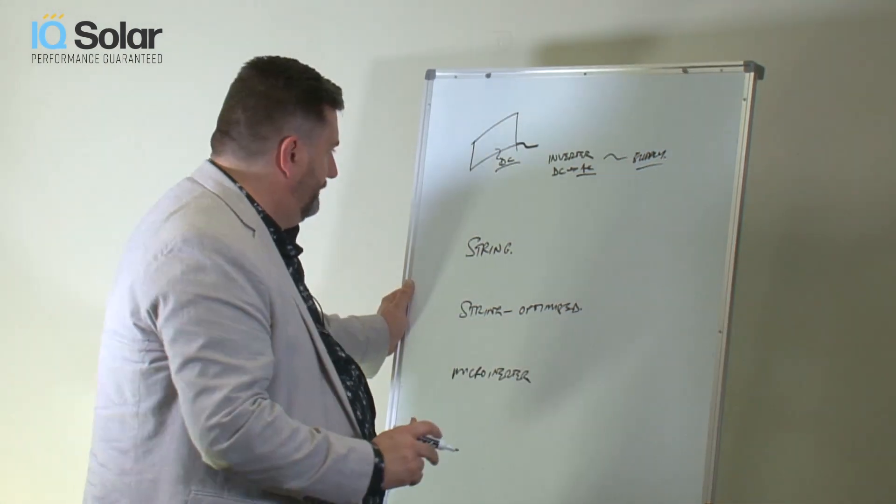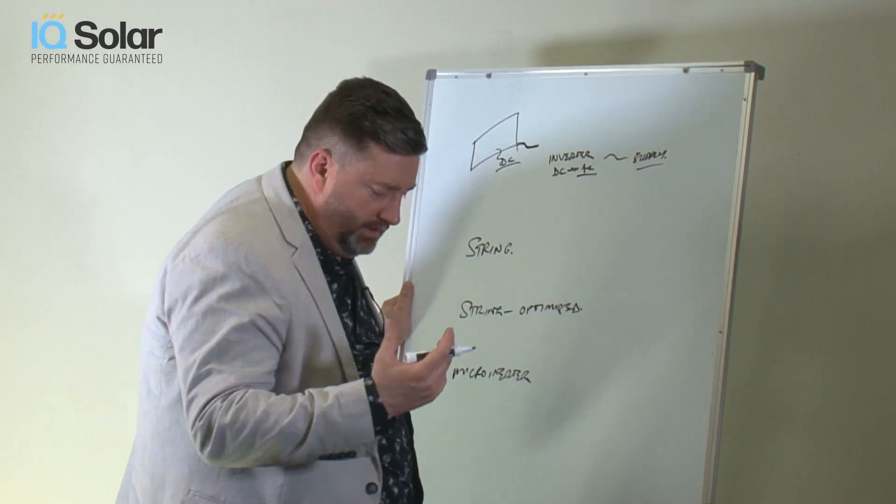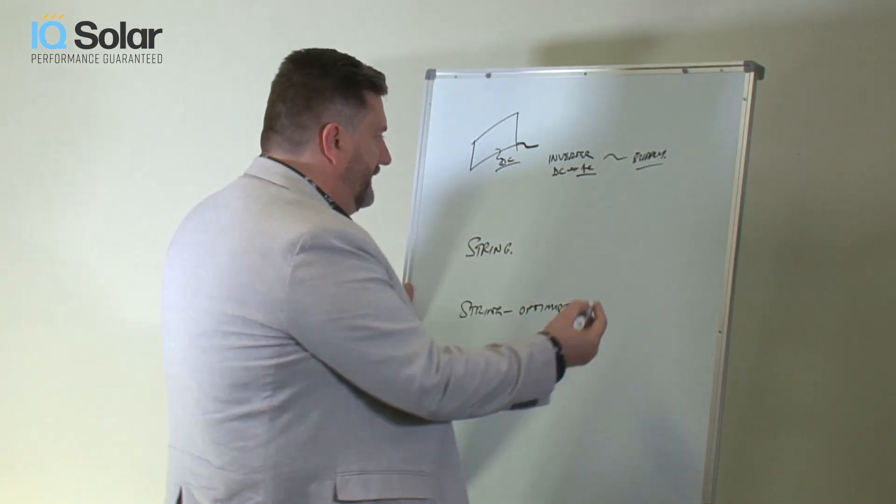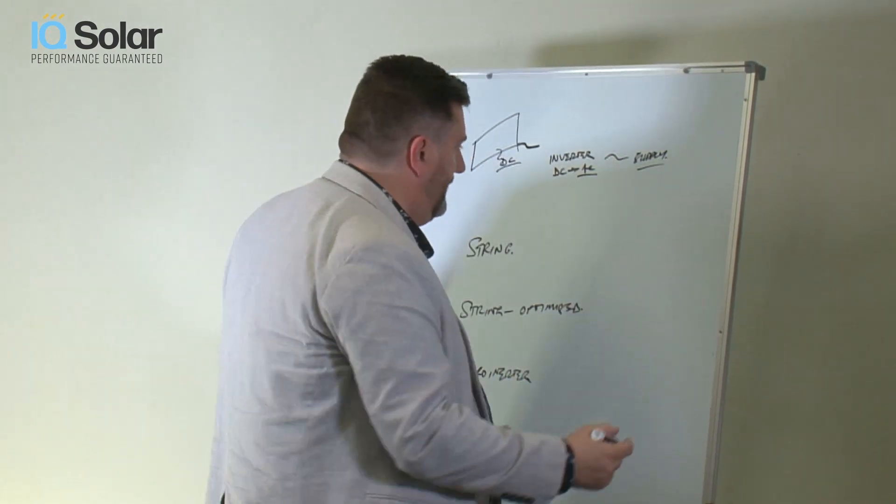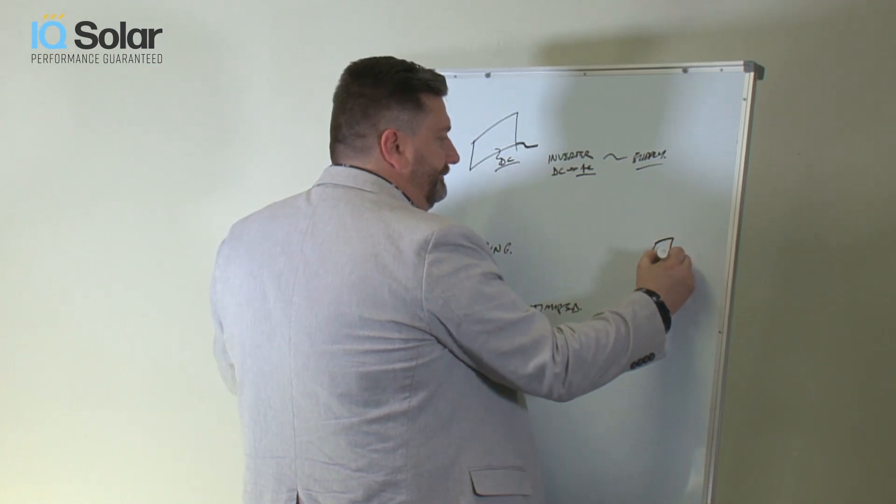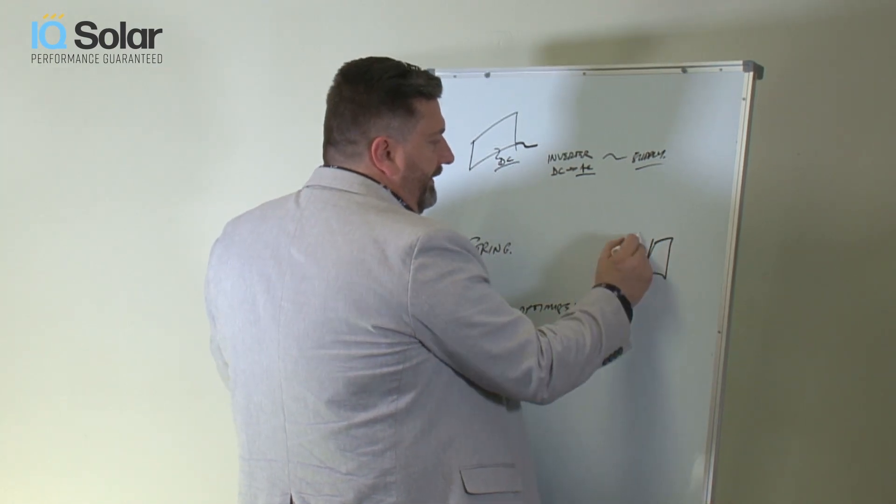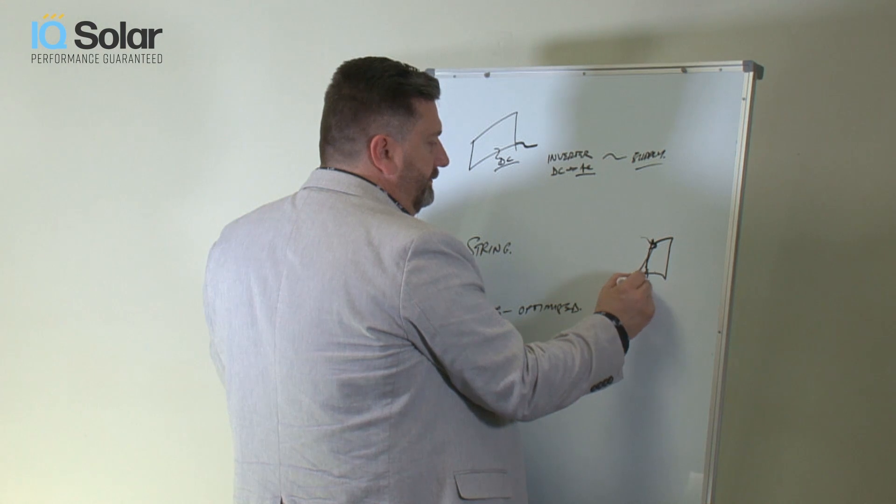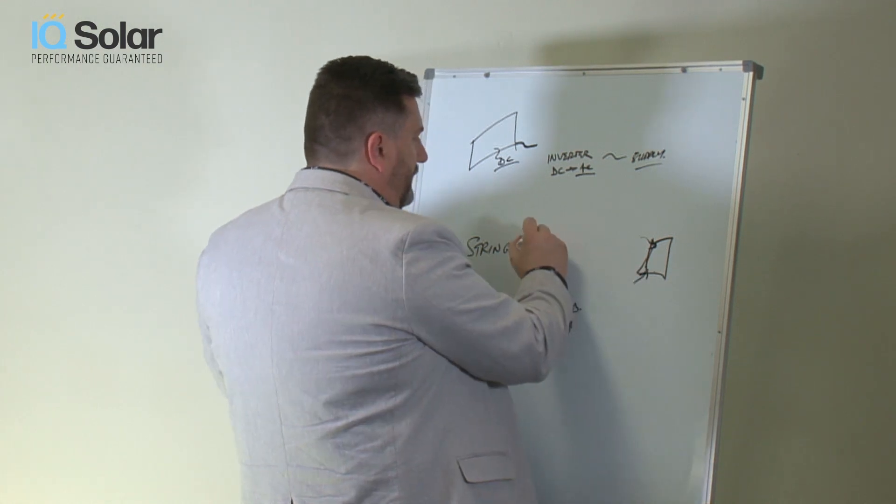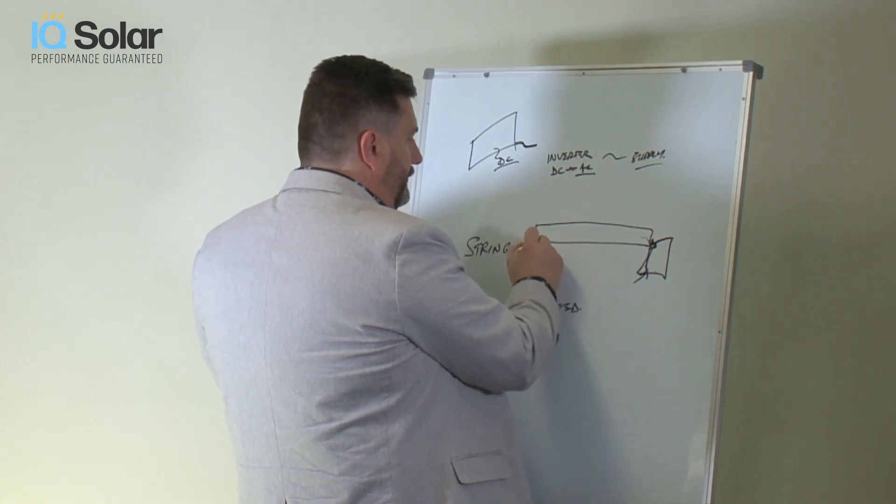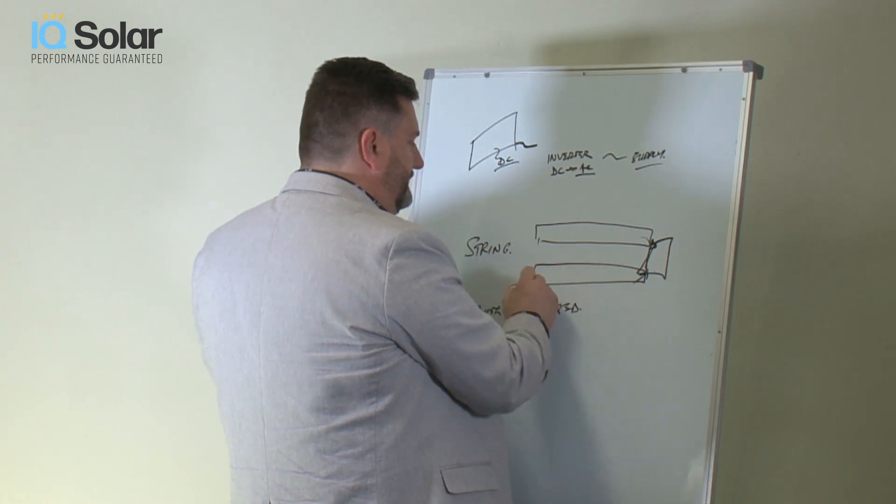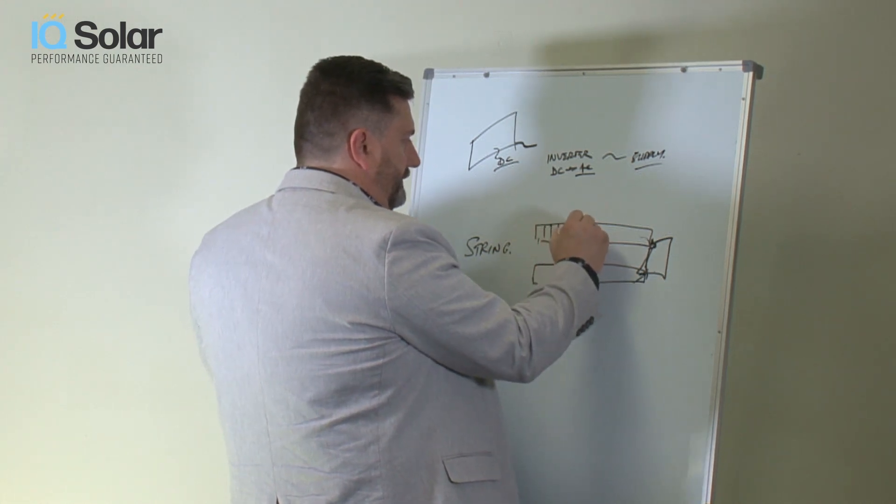So with a string inverter, let's say we were looking at a reasonable sized system, 10 kilowatts or thereabouts. You might have an inverter. There are two inputs into this, which are called MPPTs. And with each, you can have two independent strings.